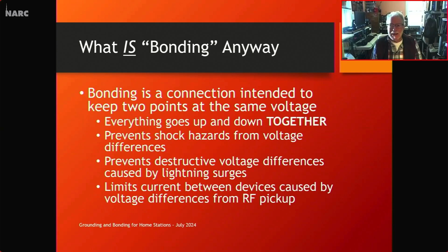and that helps reduce RF interference. Okay, if you're going to approach bonding, and to be successful at bonding, it has to be low impedance, and it has to be electrically short at the frequencies of interest, so your conductor doesn't start acting like a transmission line. And that generally means much, much less than a 20th of a wavelength, so that any phase difference across this connection is minimized. It also has to be heavy enough to carry the expected current. If we're talking about grounding in an audio circuit, these do not have to be heavy conductors. But if you're talking about bonding for lightning protection, then it might have to be a very heavy conductor indeed. So it doesn't vaporize basically when a large current surge goes through it.